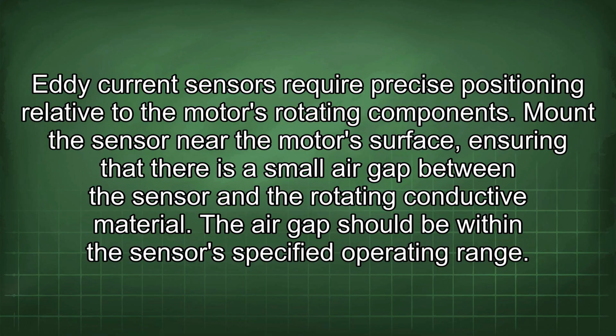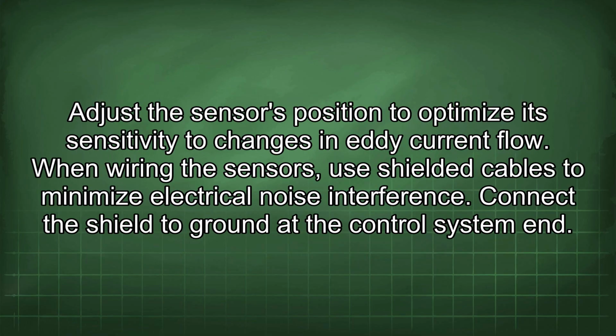Eddy current sensors require precise positioning relative to the motor's rotating components. Mount the sensor near the motor's surface, ensuring that there is a small air gap between the sensor and the rotating conductive material. The air gap should be within the sensor's specified operating range. Adjust the sensor's position to optimize its sensitivity to changes in eddy current flow.